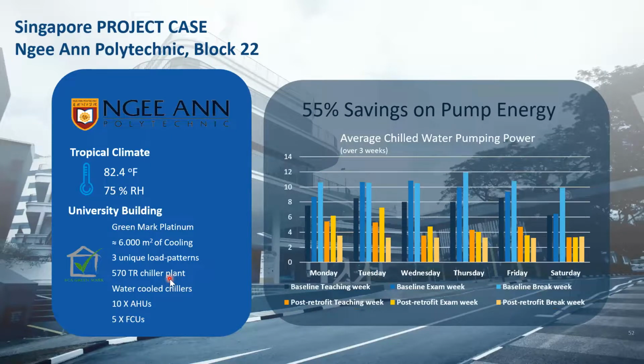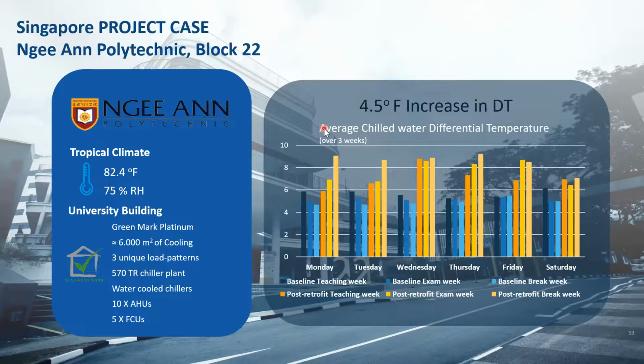And then when we look at our energy savings, we've had the ability to look at this with the different conditions in the buildings. We have teaching weeks, exam weeks, and then break week. We've had full occupancy, partial occupancy, and then some breaks. So as we look at that through the different days of the week, by combining all of that, we're able to see an overall 55% energy reduction on pump energy. Looking at the same comparison, that same occupancy use case, you'll see a little bit of differences. When we were off, we really maxed out our delta T, and when we were operating, we were still able to improve it by 30%.